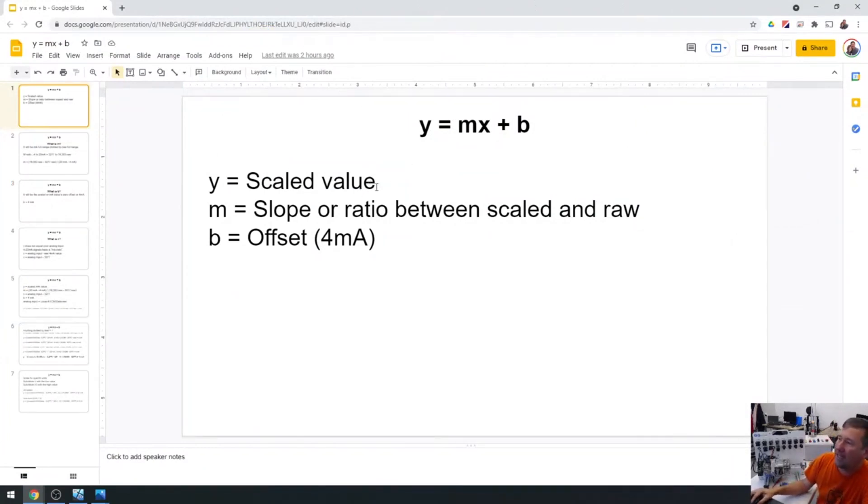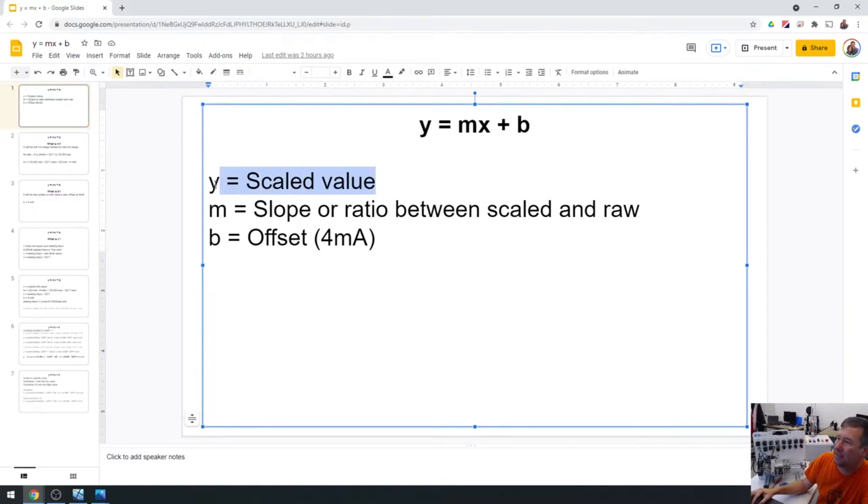And so our Y is our scaled value. So in this case, what I want to scale this to is I'm going to scale it to 4 to 20 milliamps. So I want this to end up being 4 to 20 milliamps. Now, I know usually you wouldn't make it 4 to 20. Usually it's going to be some real value. But let's start there just so we can understand it.